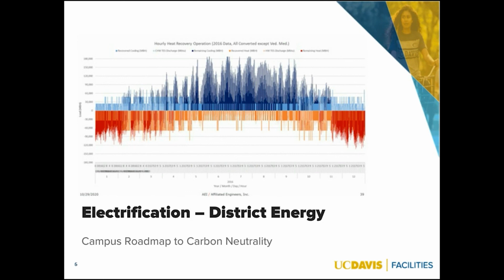When you have a district cooling system, that is probably your best source of heat, because that district cooling system, like our chilled water system, is collecting heat from the buildings. That heat right now is getting thrown away in our cooling towers to the atmosphere, but that's a huge potential source of heat if you can get to a lower grade heating like hot water.